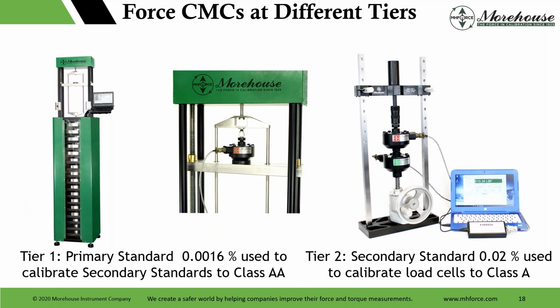So when we're actually using equipment to make different measurements, primary standards right here, this is our equipment. If we start at 0.0016%, weights calibrated directly by NIST, and then we calibrate a load cell, that load cell is then used in another machine. That other machine, probably the best we're going to get is around 0.02%, and it depends on how many transfer changes we make. One load cell by itself is not going to have the range that most people think it will, meaning if I want to maintain 0.02% of applied force, I'm likely going to need a lot more than just one load cell throughout a range to do that.